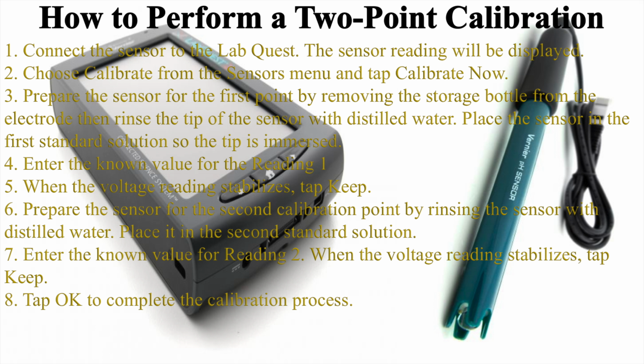6. Prepare the sensor for the second calibration point by rinsing the sensor with distilled water. Place it in the second standard solution. 7. Enter the known value for reading 2. When the voltage reading stabilizes, tap Keep. 8. Tap OK to complete the calibration process.